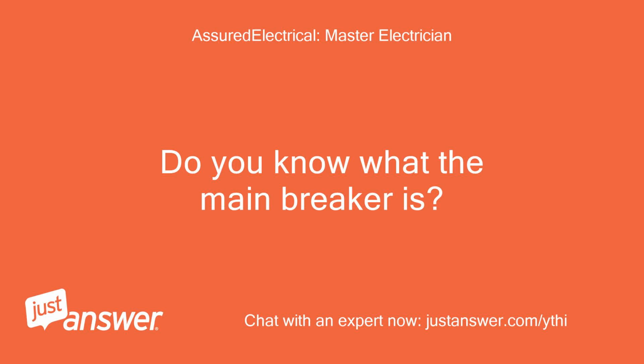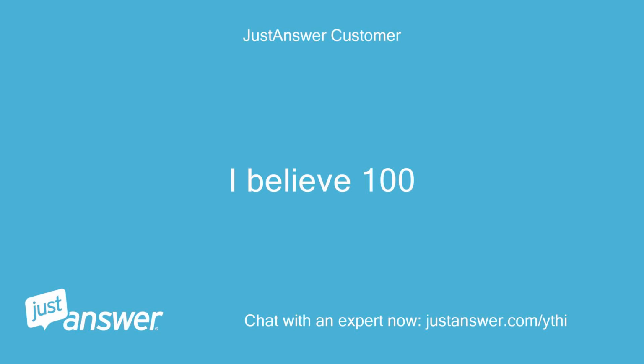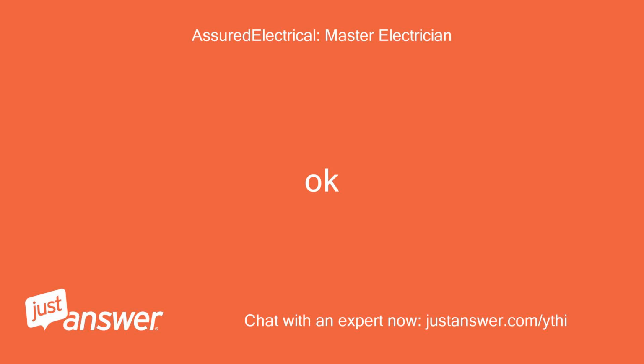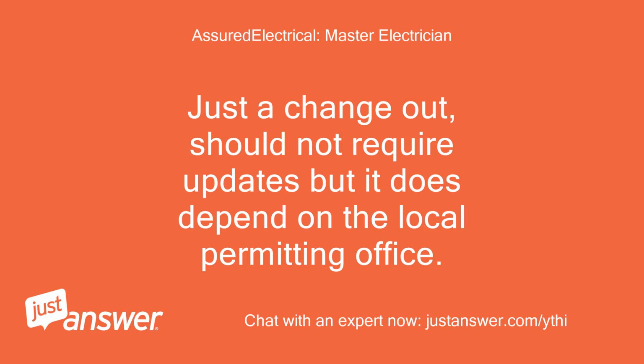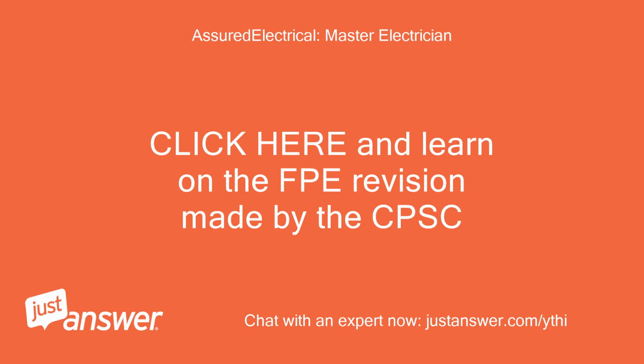Do you know what the main breaker is? 150? 200? 100? I believe 100. Okay. Just a change out should not require updates, but it does depend on the local permitting office. Estimate on change out alone in the $700 to $900 range. Click here and learn on the FPE revision made by the CPSC.